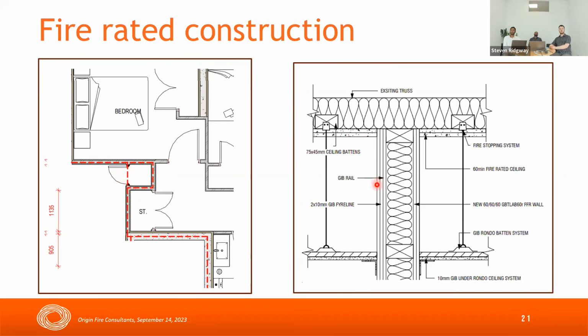And if you look here, you just see a cross section of a wall, a plasterboard wall. That system achieves an FRR of 60/60/60. This is a system from one of the manufacturers, and if you install that wall according to their system, that's the rating that it will achieve. Here they have two layers of fire plasterboard on each side, and the architect has shown what type of insulation and framing needs to be installed. So that's the second step.